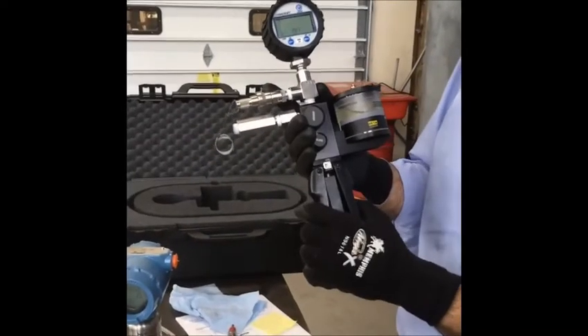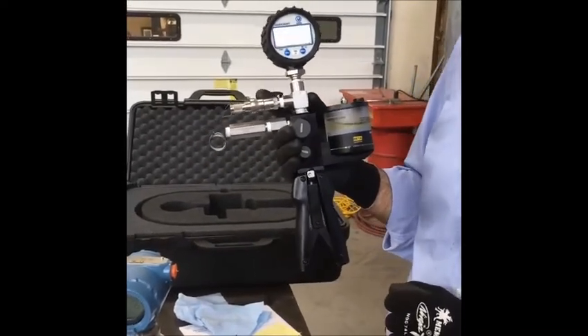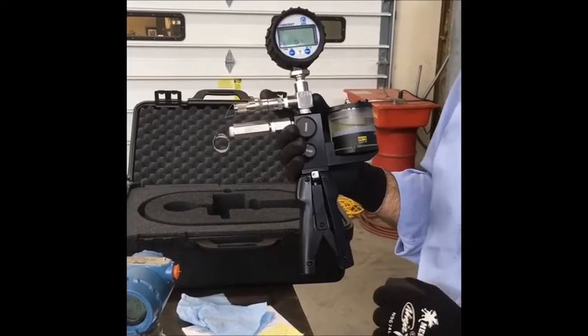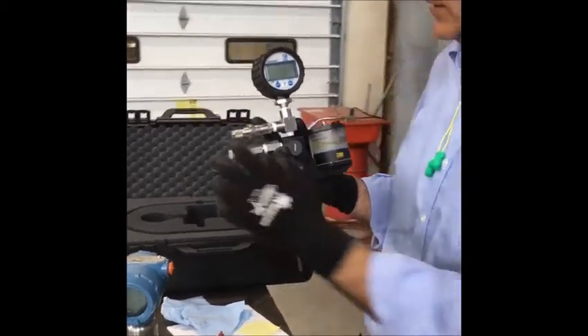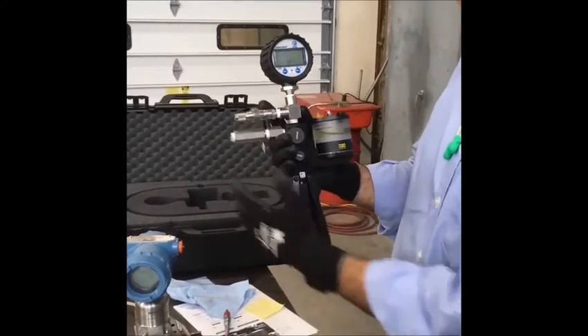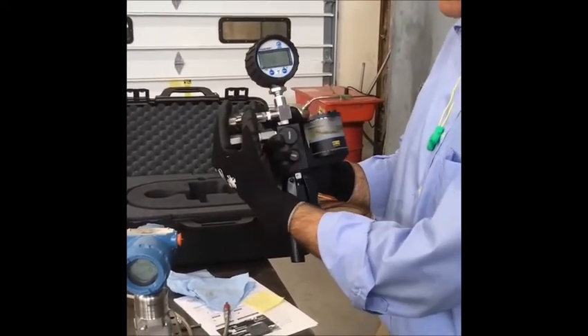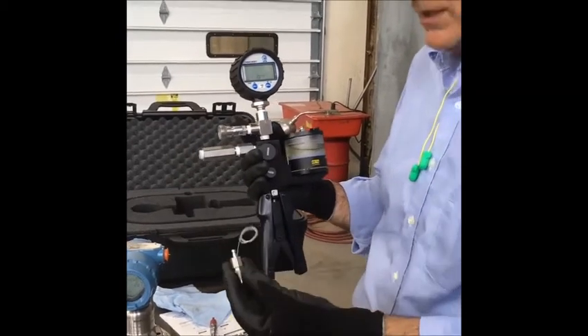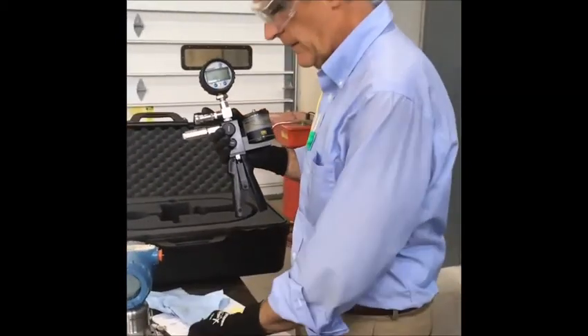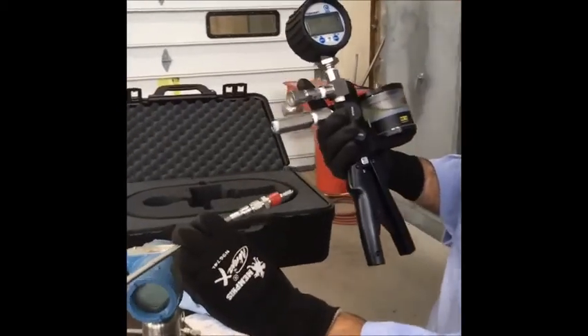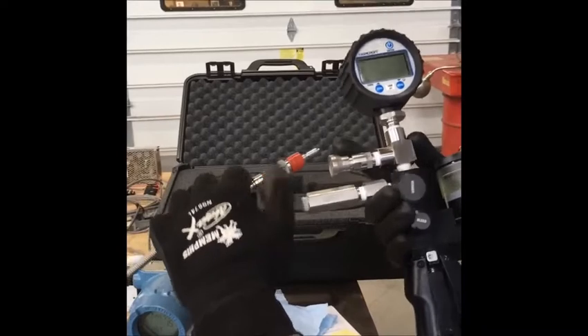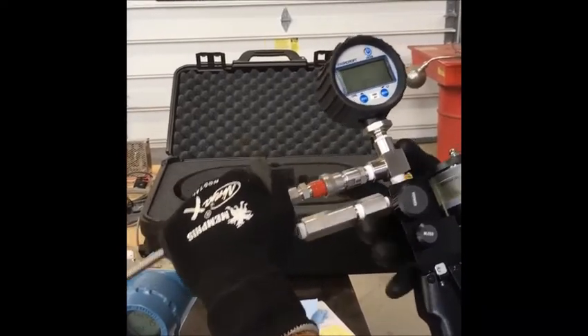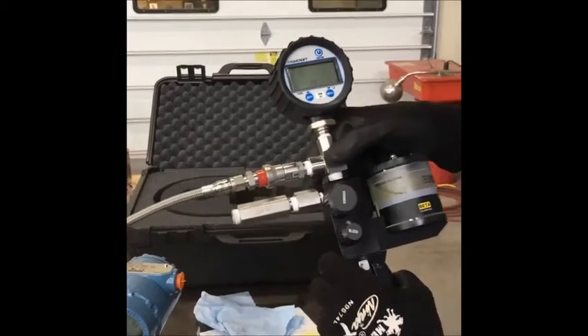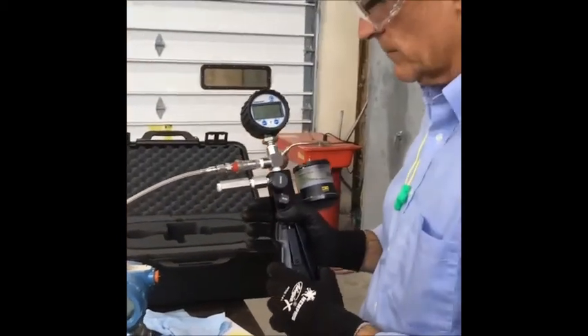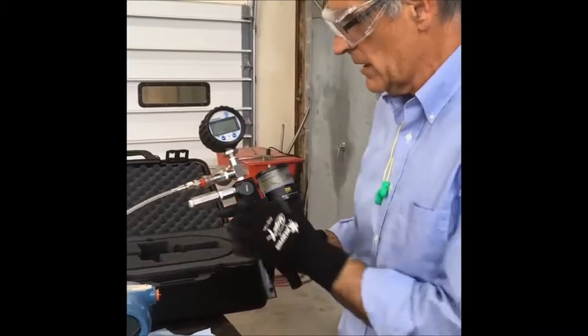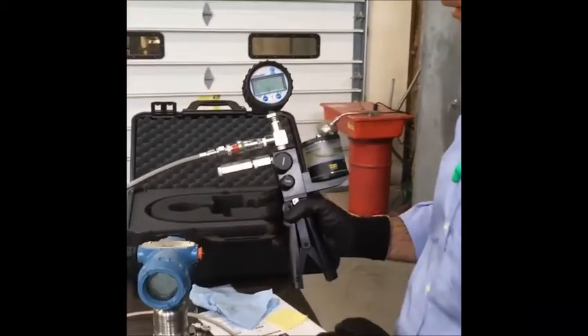We recommend that you're wearing your proper personal protection equipment anytime you're using a calibration device. So you see I've got on my safety gloves, safety glasses. So the first step after we've got the calibration pump out is we have to remove this quick connect. It's really just to keep the pump connection clean. And then we can install the test hose, and that would be the short end of the test hose, into the calibration pump. So we insert the connector in, push it in until it clicks, and then we're ready to go on that end.